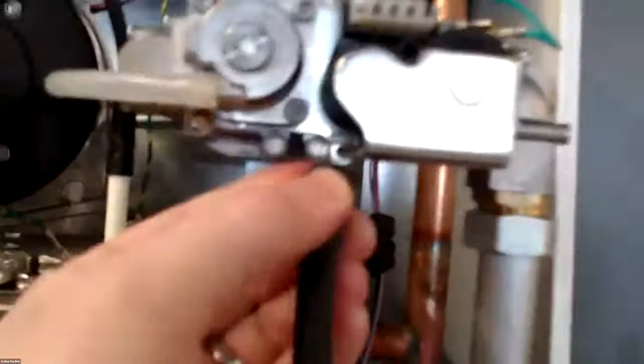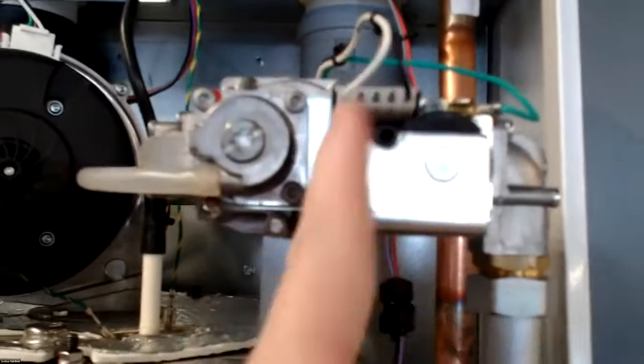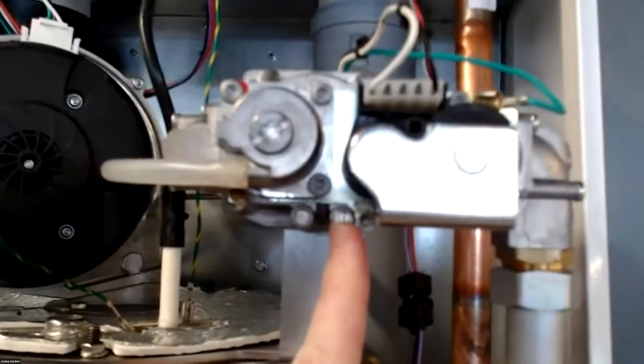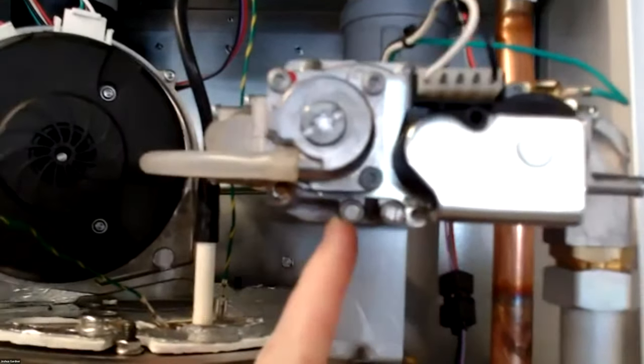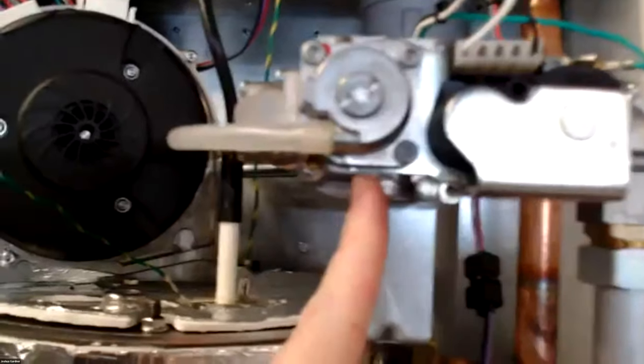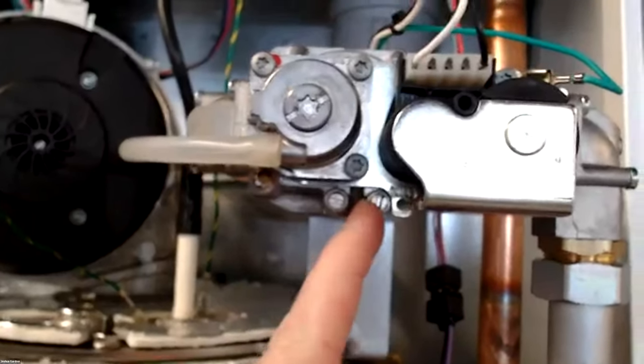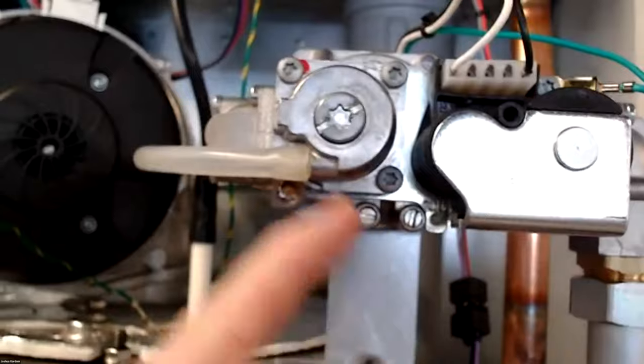Gas valve, turn the gas off for a second. So gas valve, gas comes in right here, grounding wire, voltage into the gas valve, our solenoids, incoming gas pressure, offset. Don't really use the offset for much testing. Most of the time we're just using the inlet gas pressure.